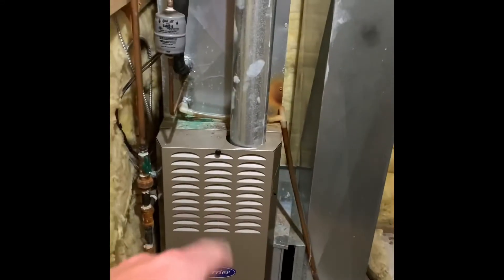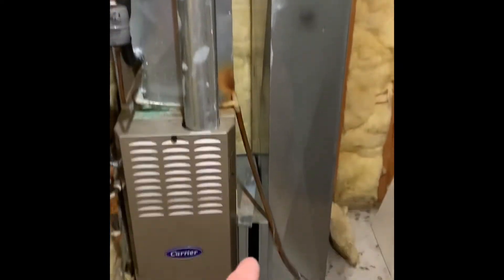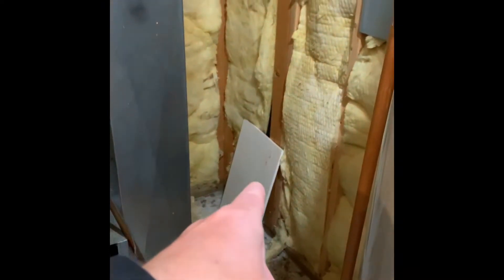Here's our inside portion. We're going to keep the furnace, new air conditioning system, new coil. Bring a 16 by 20 by 1 filter. I'm going to replace the lines — they go up and over. There's a refrigerant leak, but the AC sits right outside there. Panel box is here, it's marked for double pole 30.